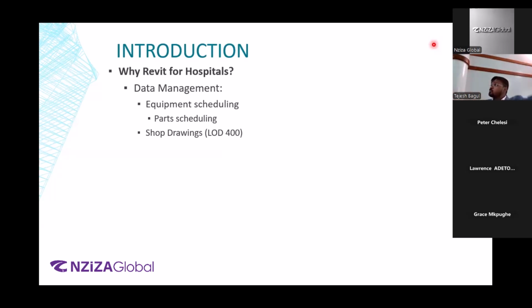Okay. We spoke about the different phases, right? We spoke about SD phase, we spoke about DD phase, we spoke about CD phase, construction administration phase earlier, right? So think of this as tying up into that. When you're talking about schematic level design, the level will be LOD 100. When you go into design development, you'll progress into LOD 200. Basically, if you have a bigger duct and you're fine-tuning that duct, that will come into picture. If you have insulation wrapped around the duct, that will come into DD phase, basically LOD 200.